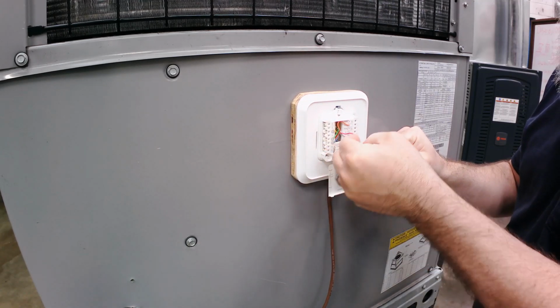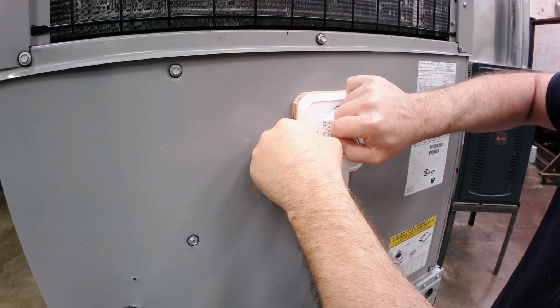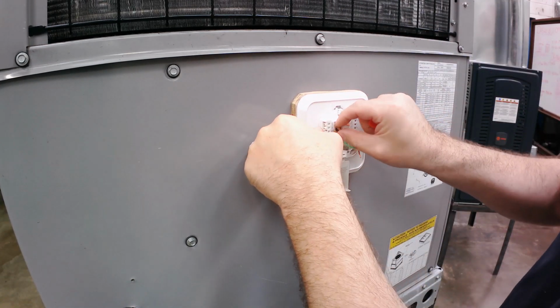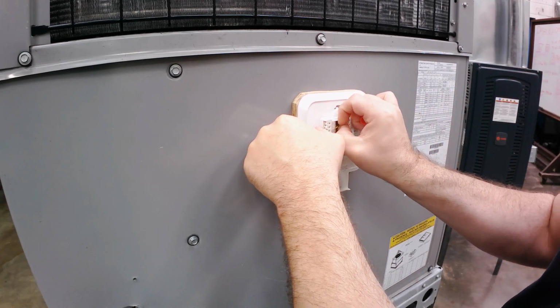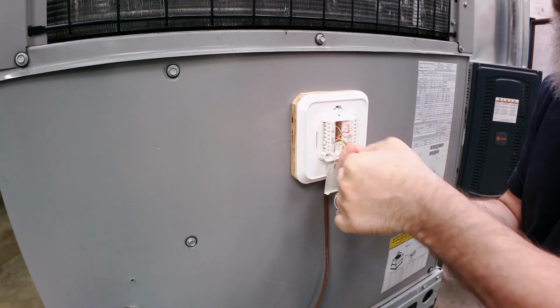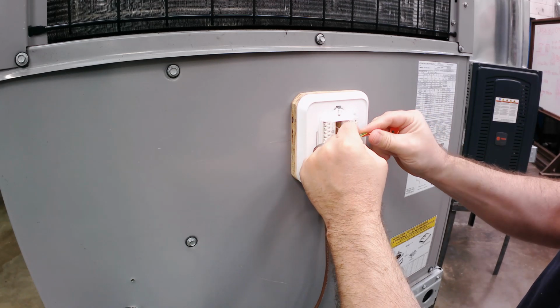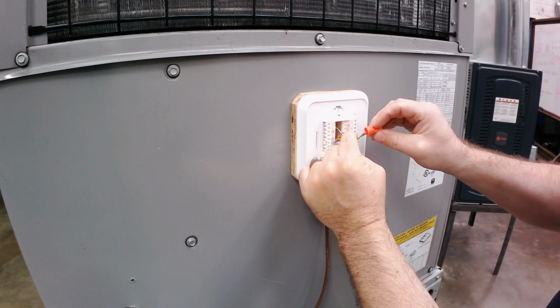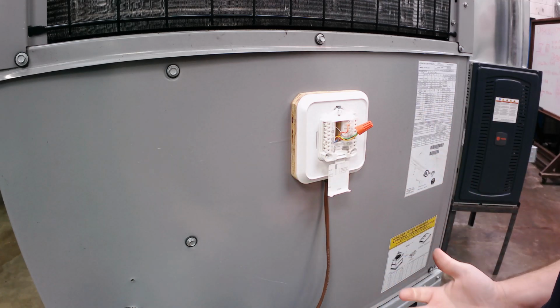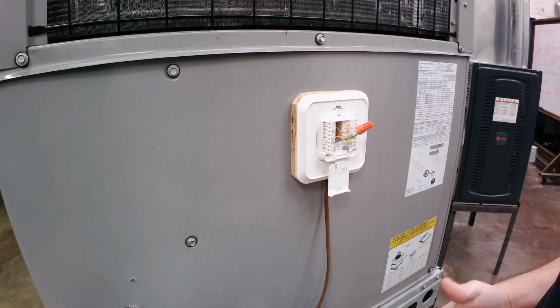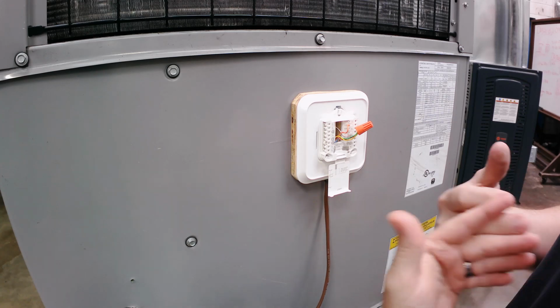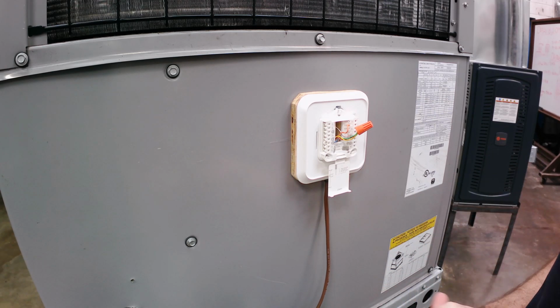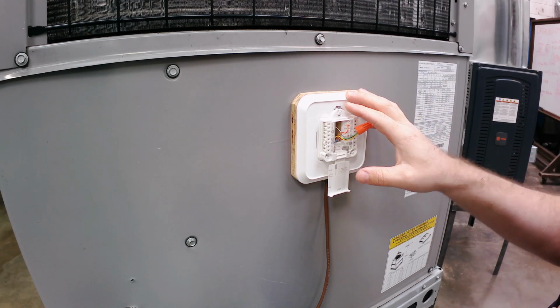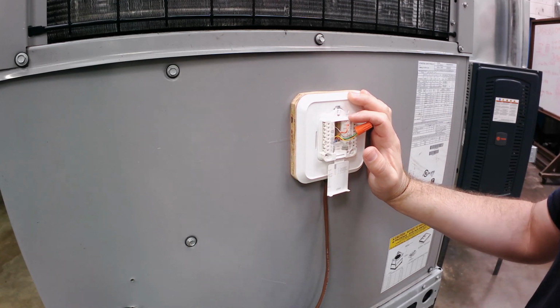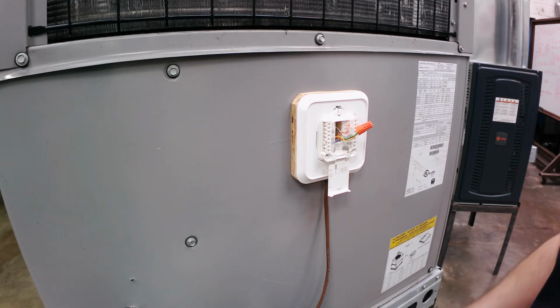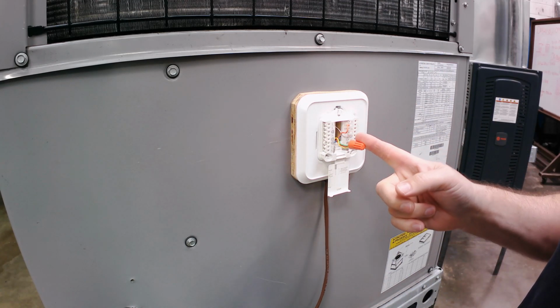Since everything comes from R, all you have to do is pull out the circuits you want, except for the common. Take all those circuits right there at the thermostat, and if you lined up the wires well, take a wire nut and use it in place of that thermostat switch. If you think it's a bad switch, jump it out—that will let you finish troubleshooting, finish checking. I'd hate to run to town just to grab a new thermostat and then find out I also need a new contactor or capacitor or something like that. So troubleshoot as far as you can. In the case of the thermostat, we can rectify that problem with a wire nut.